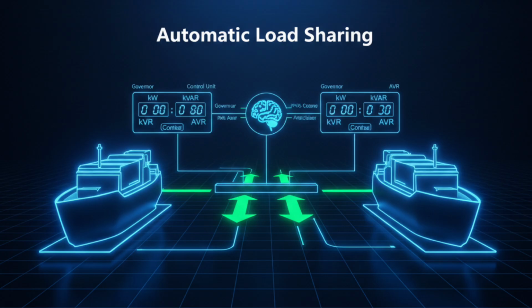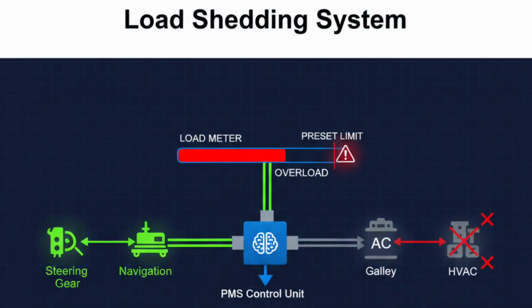Operators can monitor real-time load percentages on the PMS HMI screen, making it easier to track and troubleshoot any issues. Automatic load sharing is not just about convenience, it's a critical safety feature for modern ships with automated electrical systems. Load shedding is the automatic disconnection of non-essential loads when generation capacity is insufficient.